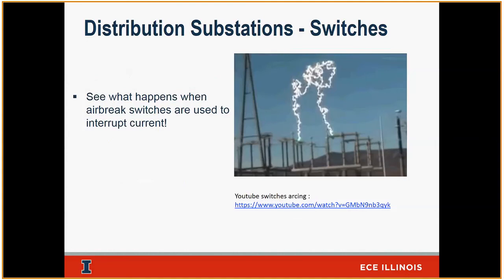They pick up the phone or the wireless or the cell phone and call this guy and say, okay, I de-energized a 69 kV line for you. Test it, make sure it's de-energized, and then go ahead and open the switch. These commands have a specific language, specific instructions, mainly for the safety of the coworkers that we've got. So he's standing in line here, waiting. He gets that instruction. He tests his line, makes sure it's not hot anymore. Then he will go ahead and open that device and de-energize it. That language, that world, we call WPA, Workers Protection Application. So that's what we call it. And it's got a book, and everybody runs by the book. If you deviate, very bad consequences will happen.